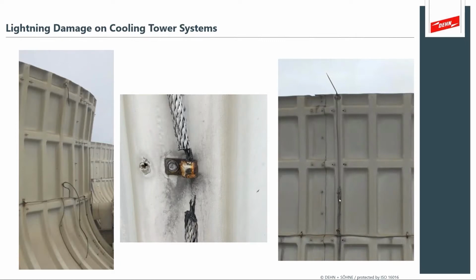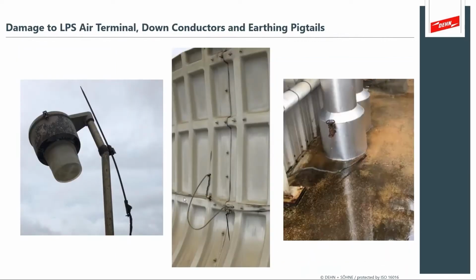So damage at power generation facilities takes a lot of forms. In this photograph, you can see there's actually a lightning protection system. It's a bonded system directly on the vents of these cooling structures, and you can see damage that gets incurred. This is possibly the result of a lightning strike that actually hit the cable and caused the cable to be severed. And you see a variety of damage that looks like that. Things like air terminals mounted on lights where there's insufficient separation distance. Here you see examples where the cooling tower might have been struck itself, and it's caused the air terminals to become disconnected and basically fall off the structures, all the way down to the base where you see the earthing pigtails being severed. These are all possible types of damage that would be incurred from lightning strikes.